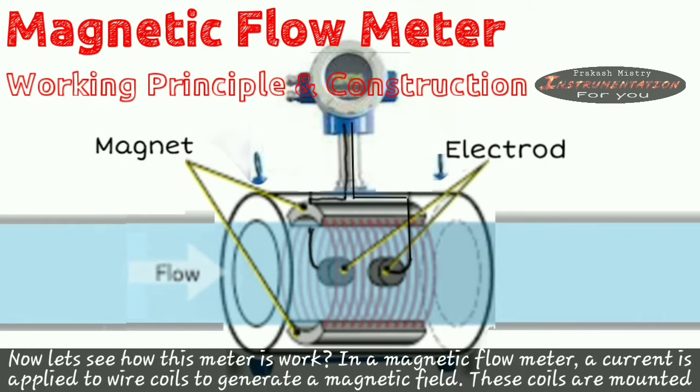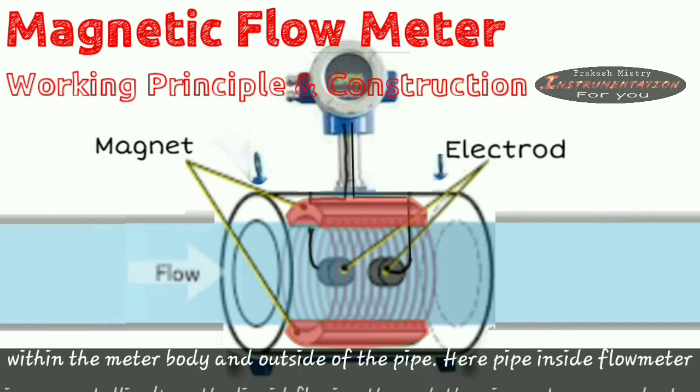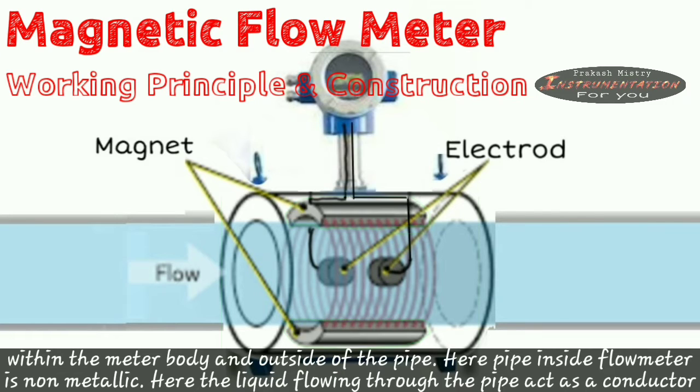Now let's see how this meter works. In a magnetic flow meter, current is applied to wire coils to generate a magnetic field. These coils are mounted within the meter body and outside of the pipe. Here pipe inside the flow meter is non-metallic.